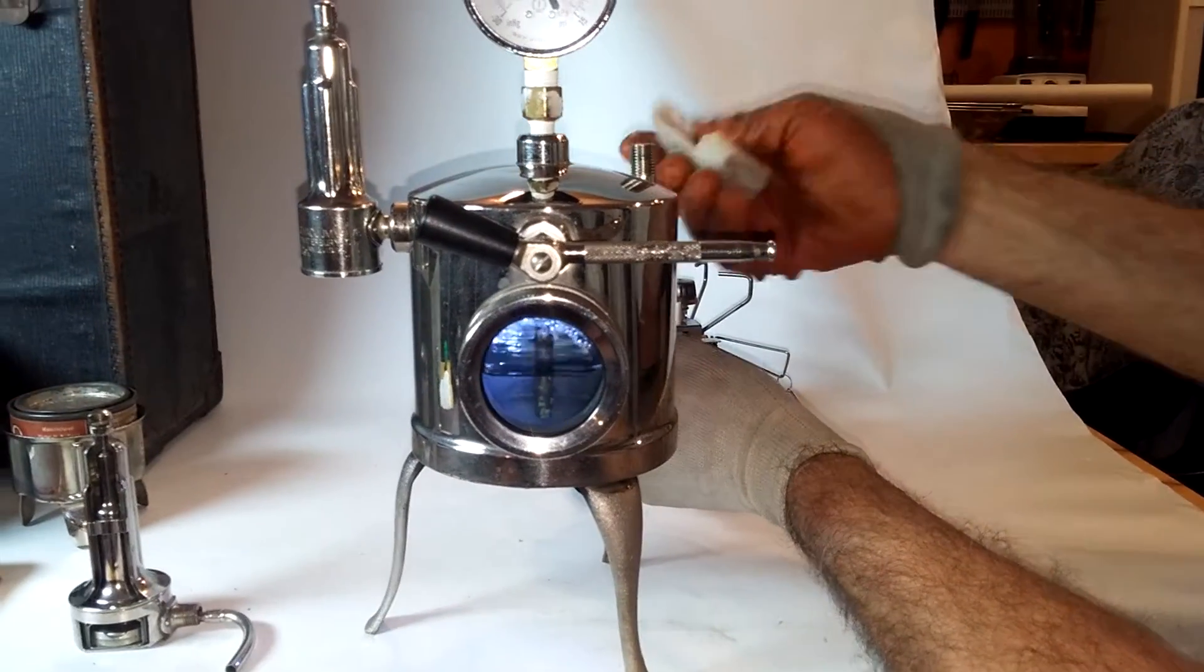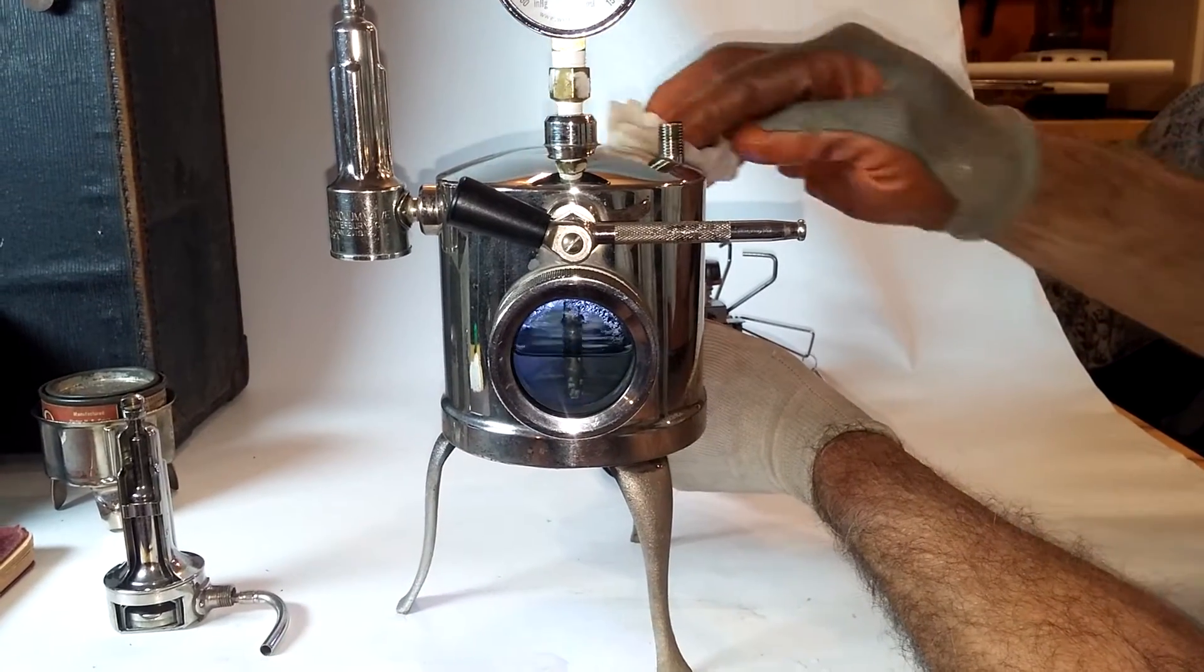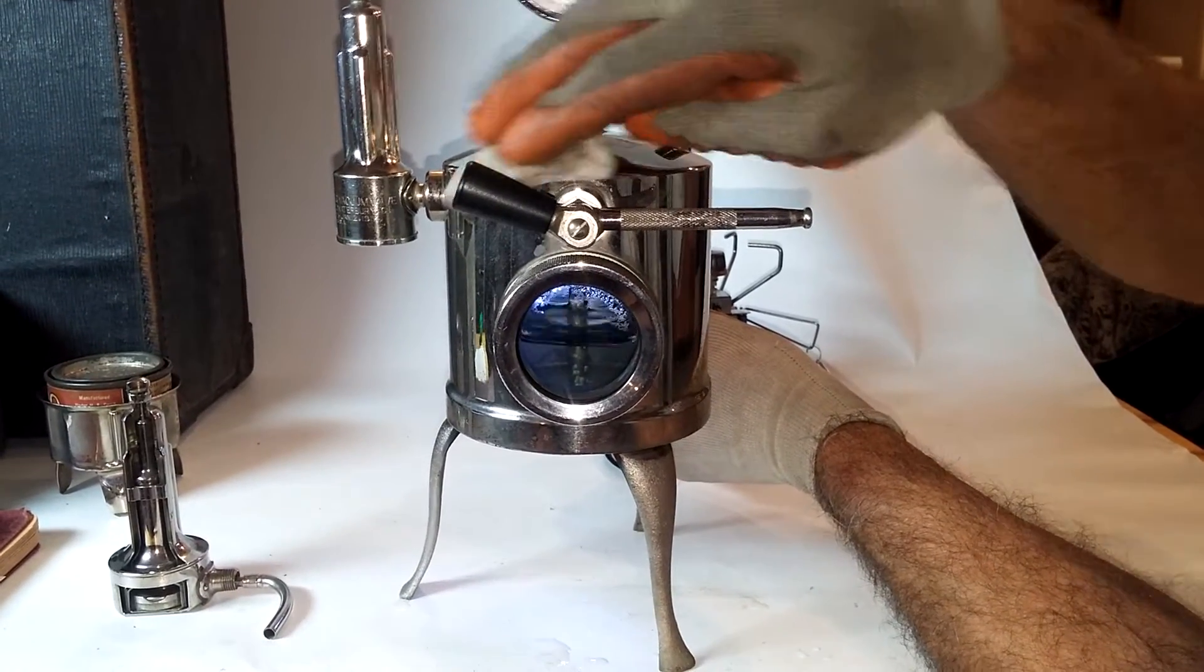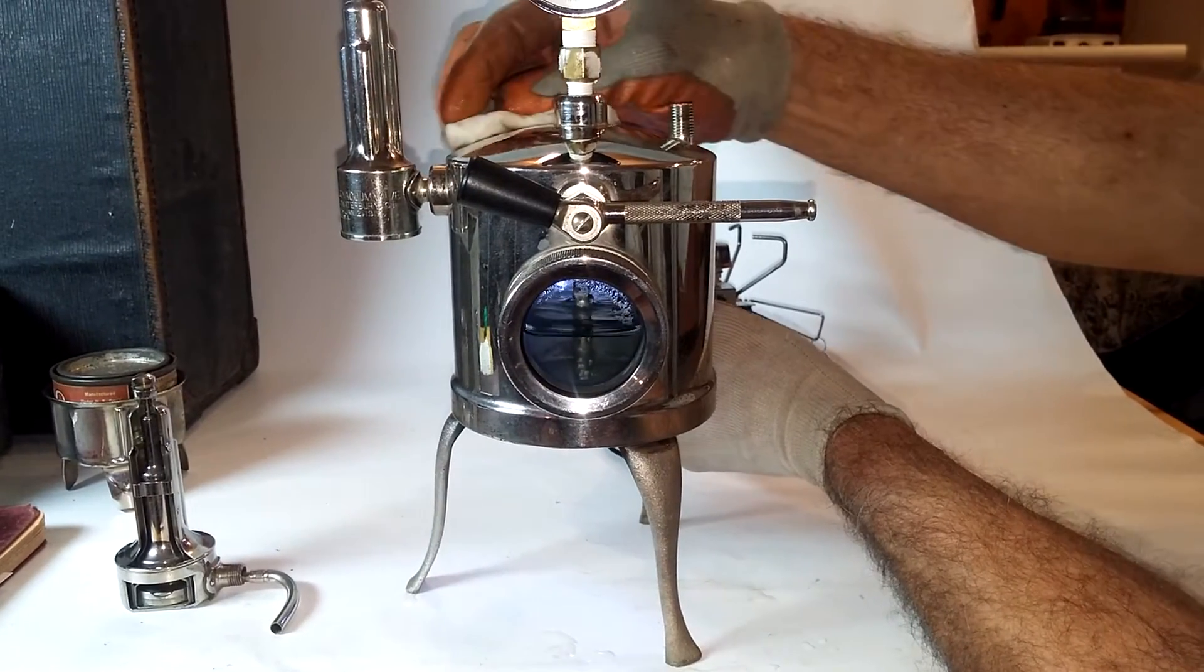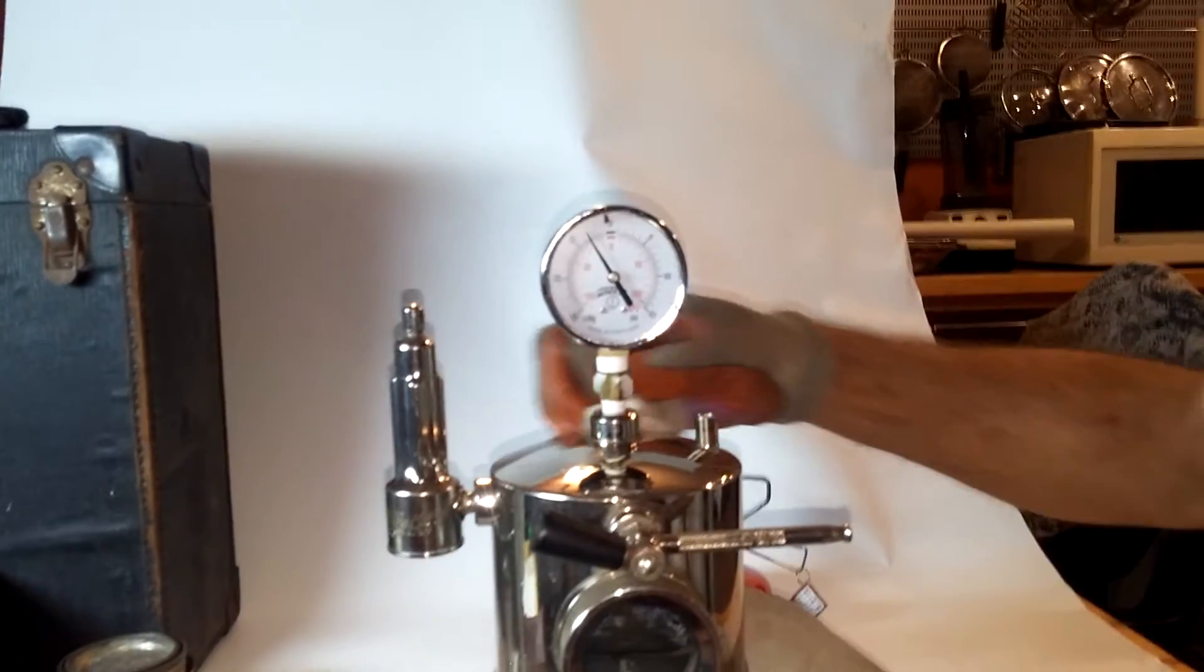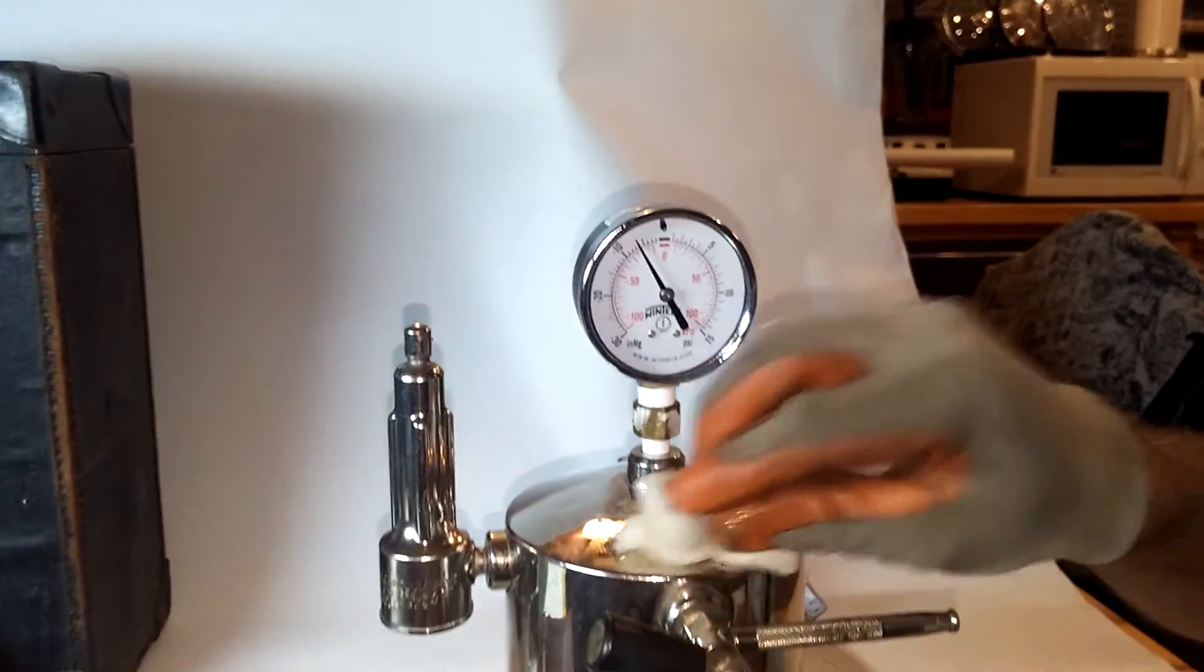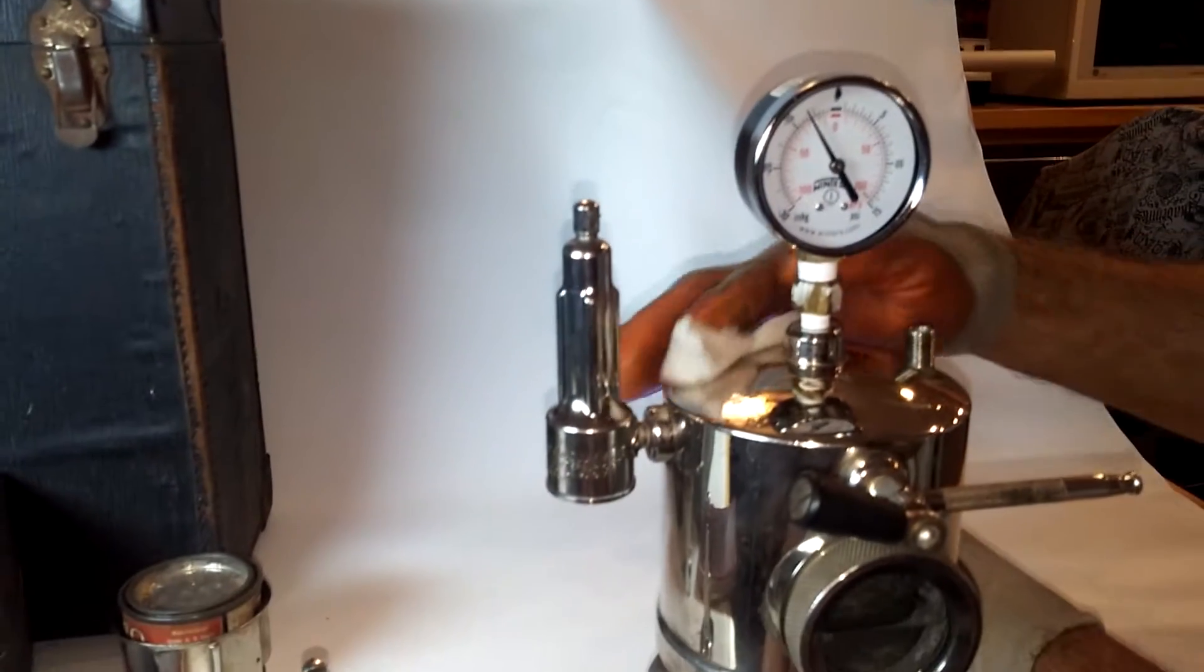I've gotten this thing down as low as 15 inches of mercury on a really tight system, and the water continues to boil as the pressure drops, as the heat is extracted from the water.